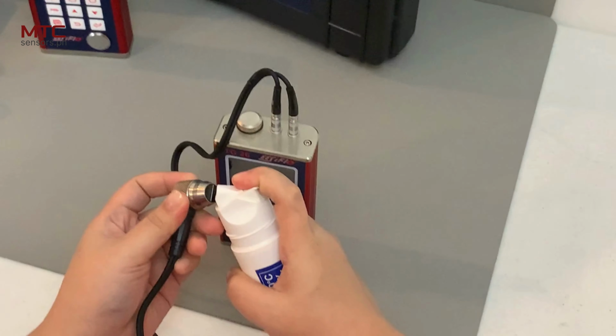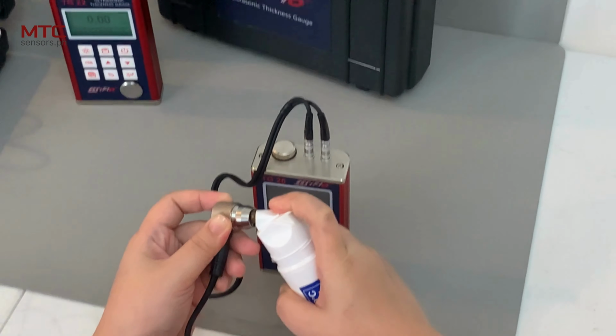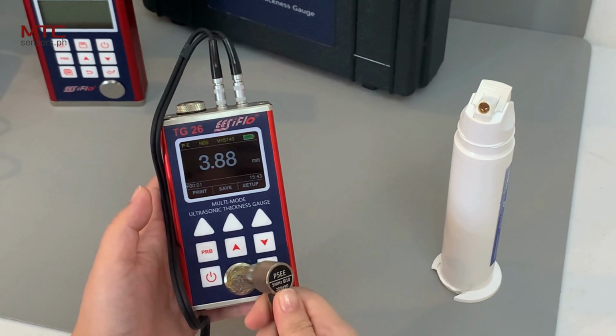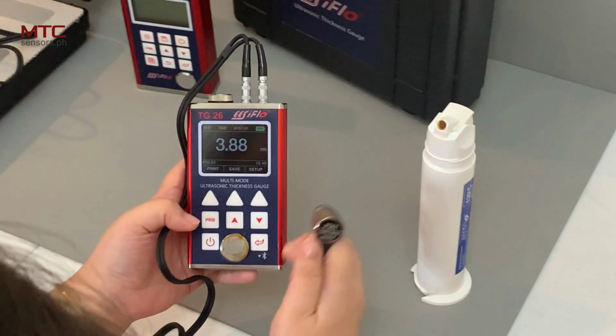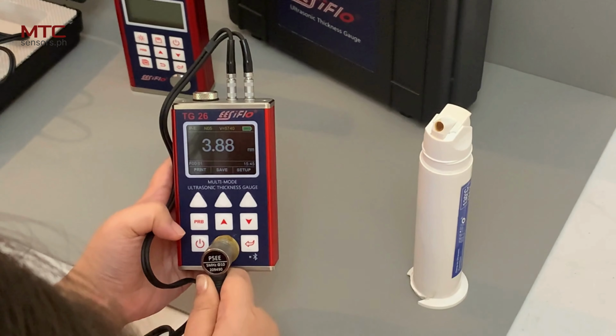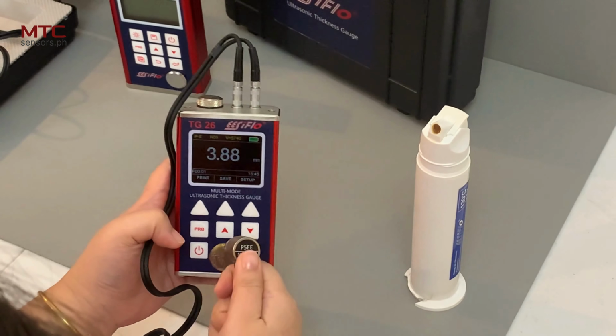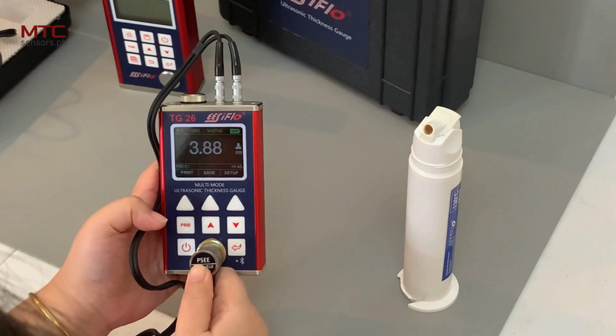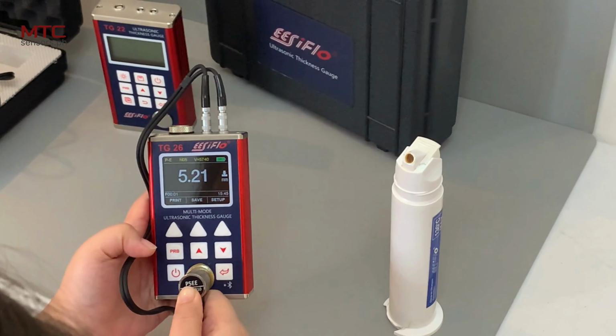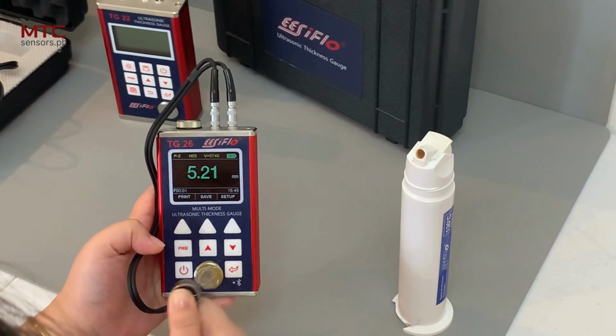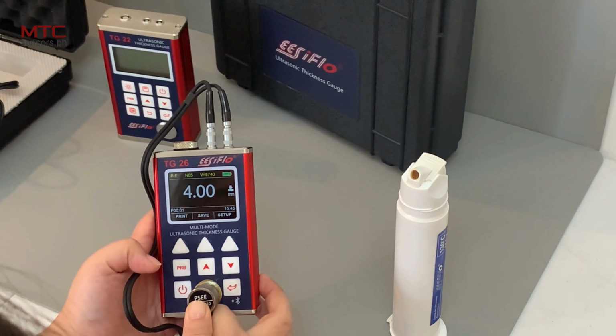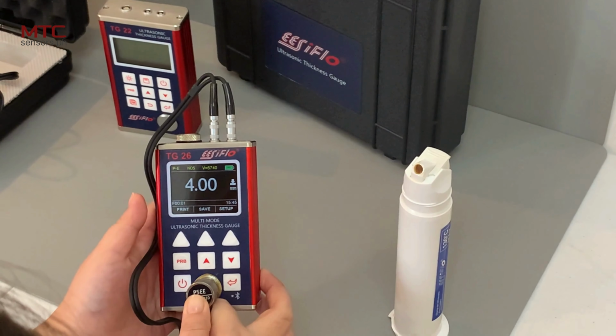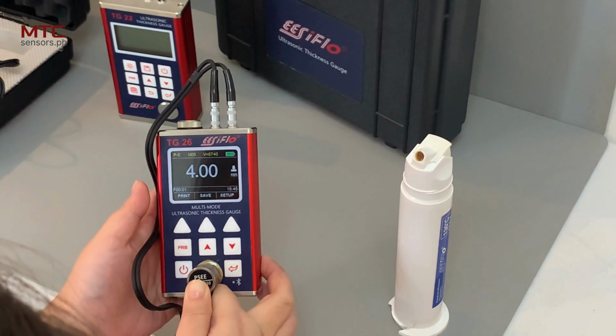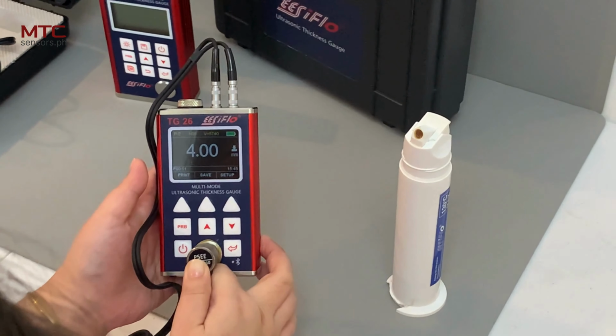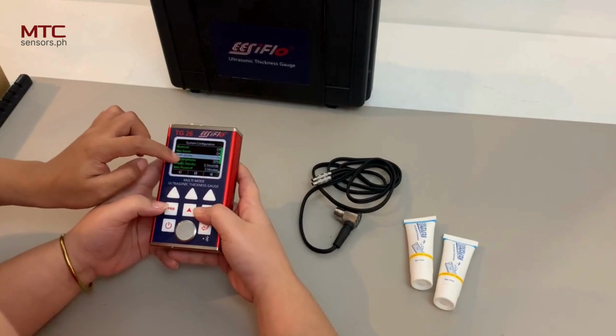To measure thickness, apply a small amount of couplant to the material and press the transducer firmly against the surface. The display will show the thickness. If the reading is unstable, ensure the transducer is flat and properly coupled. The device updates measurements every second while the transducer is in contact and holds the last reading when removed. Be mindful that leftover couplant or thick coatings can affect accuracy, so it's important to use the instrument correctly.